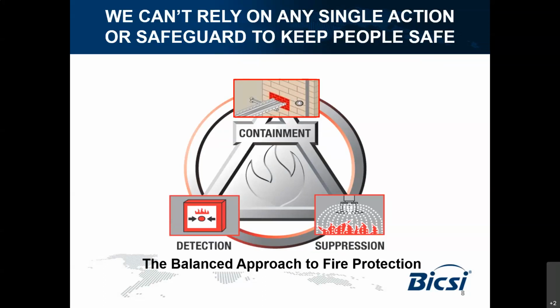That's where the fire-rated wall and floor barriers come into place. Containment is not only about penetration firestops, it is also linked to the wall and floor as the core element. But when any penetration, no matter the size, goes through those fire-rated barriers, the integrity of the wall is destroyed. The opening must be properly firestopped to restore the original integrity of the assembly. The biggest threat to damaging equipment and communication is smoke and the products of combustion, as I stated before. With just a few small holes in a fire-rated assembly, smoke can already migrate through a building in a matter of minutes.